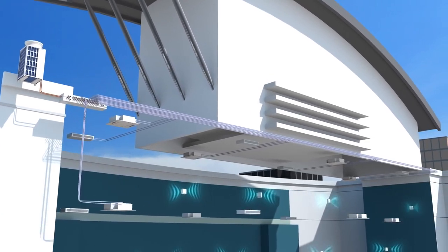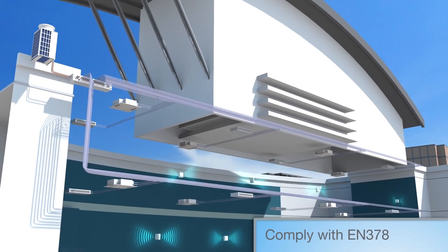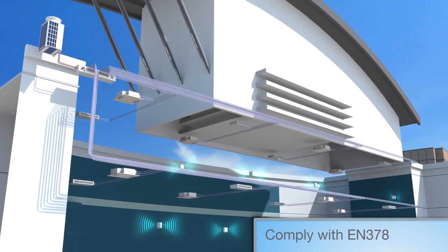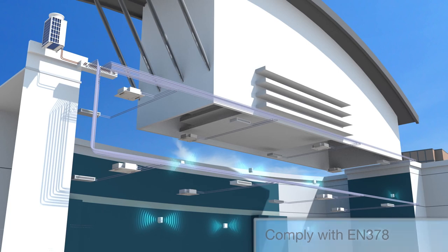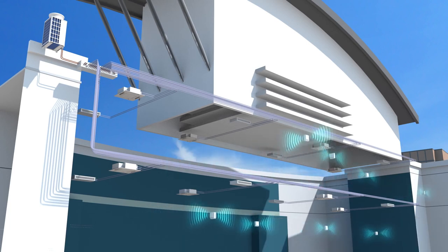water replaces the refrigerant to transfer heating and cooling energy around the building, giving the same control, the same energy efficiency, but allowing the building to comply with refrigerant legislation such as EN 378.